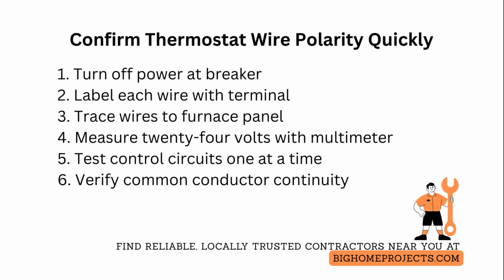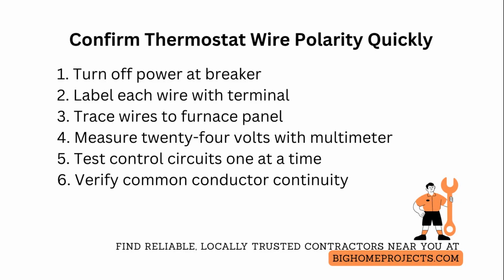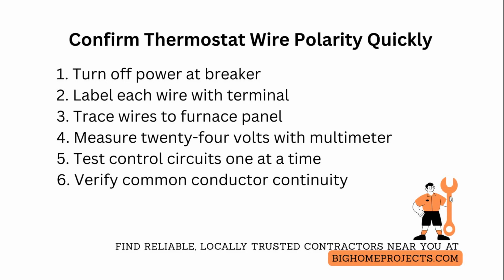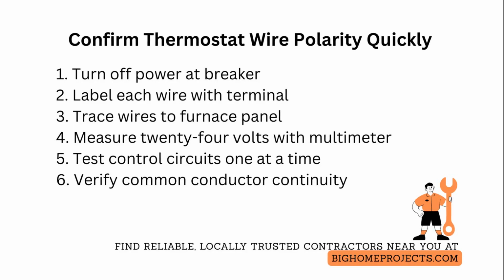If polarity-sensitive smart thermostats or thermostats that require a common conductor are involved, verify the common is continuous back to the transformer common terminal with an ohmmeter. If continuity fails, pull and re-terminate the common at both ends or add a proper common using a compatible power extender kit following the thermostat manufacturer instructions.